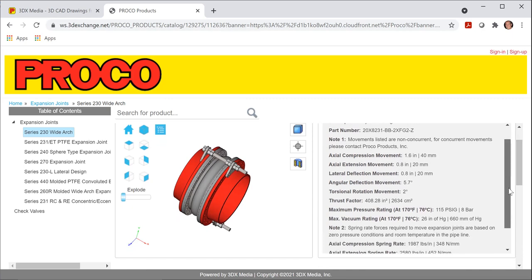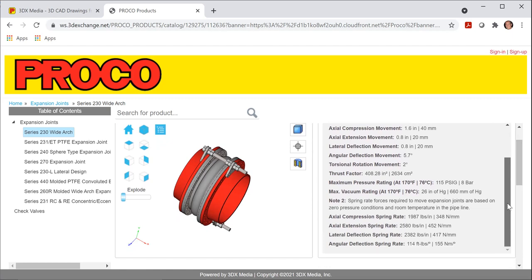thrust factor. And then if you scroll to the bottom, there's different types of spring rates as well. So all of this information can be input into your stress analysis system and will give you a better idea of what introducing an expansion joint into your piping system will do.